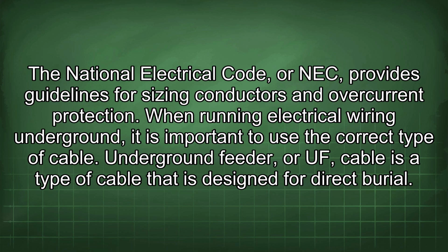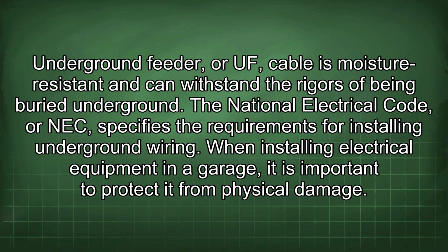When running electrical wiring underground, it is important to use the correct type of cable. Underground feeder, or UF cable, is a type of cable that is designed for direct burial. UF cable is moisture resistant and can withstand the rigors of being buried underground. The National Electrical Code, or NEC, specifies the requirements for installing underground wiring.